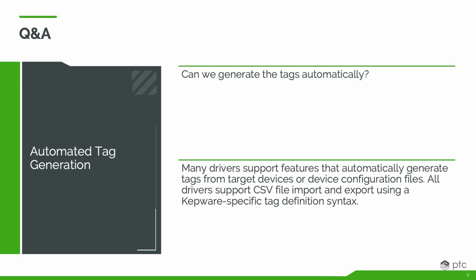This is true for Siemens S7 PLCs, the 1500s and 1200s, where we support the latest standard with automated tag generation. Rockwell Automation's Logix series, BACnet devices, Omron devices, and many other standards now allow us to automatically create variables inside Kepware. You can also kick off that automated ingestion programmatically by calling an API endpoint, and we can generate tags on demand for you.